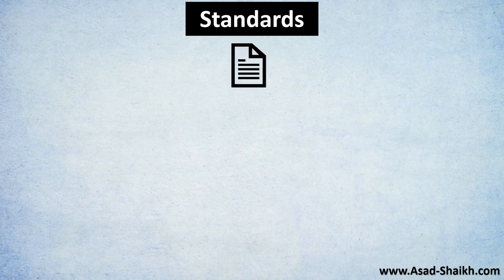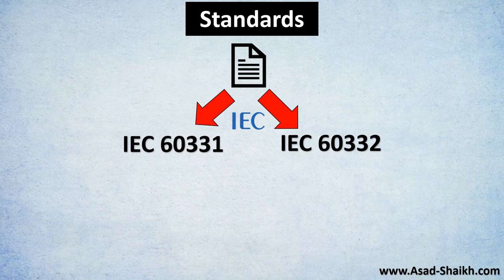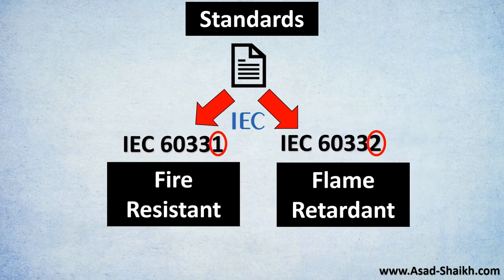In terms of standards, the two most important and widely used in the industry are the IEC standards: IEC 60331 and IEC 60332. The difference between these two lies in the last digit — the 1 stands for fire resistant cable and 2 stands for flame retardant cable. There are also other standards like BS6387, but the IEC standards are the most widely used.